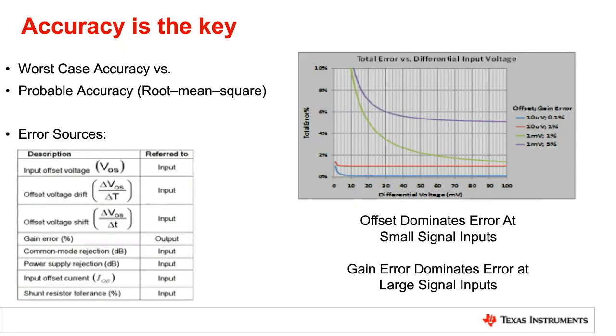So looking a little bit closer at accuracy, whenever we determine these for the current shunt amplifiers, there are 2 different ways to look at it. The worst case accuracy, which is essentially a sum of all of the inaccuracies inside the system, and then a probable accuracy, which is a root mean squared summation. So you might see both of these tossed around when looking at total system accuracy. Typically, what we're going to be interested in whenever we're designing an industrial system like this is going to be the worst case accuracy. Now, there's a lot of different sources for error inside these systems, but the 2 main ones are going to be offset error and gain error.